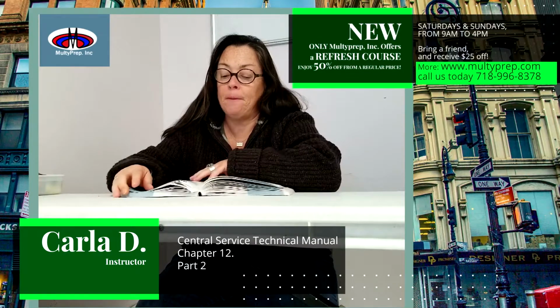Inspect for cleanliness. Even though instruments have been cleaned, there may still be instances where some soil was not removed. See Figure 12.6 for an example. Organic materials such as blood or other contaminants will interfere with sterilization and optimal functioning. Inspecting instruments for cleanliness adds a safeguard to the process by reducing the chance that a soiled instrument is delivered to a user area. If a soiled instrument is detected during the inspection process, it should be sent back to the decontamination area for prompt cleaning.